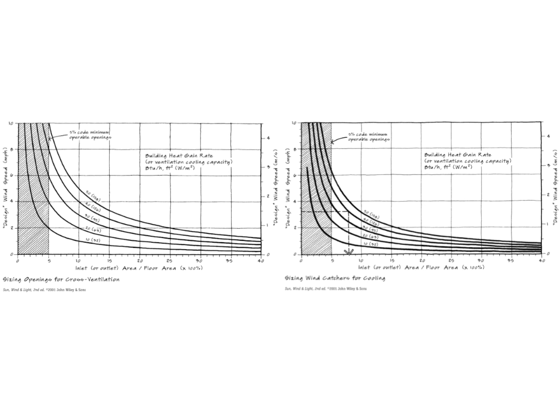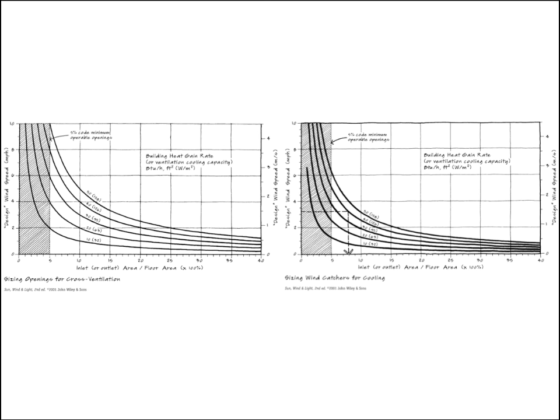Here are two sizing charts — one for cross ventilation openings on the left and one for wind catcher openings on the right. They work the same way, with wind catchers being slightly more efficient, meaning you need a little less aperture area for a wind catcher to do the same cooling job as cross ventilation. Let's take a closer look at the sizing openings for cross ventilation graph, which appears in the ventilation apertures strategy.